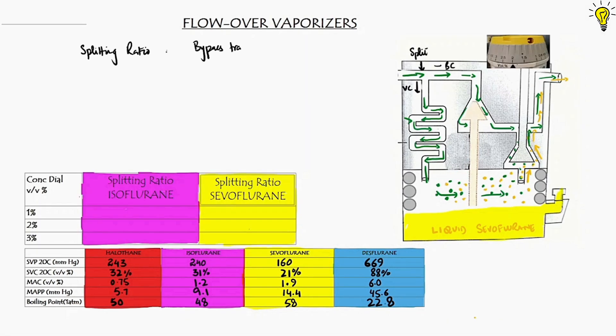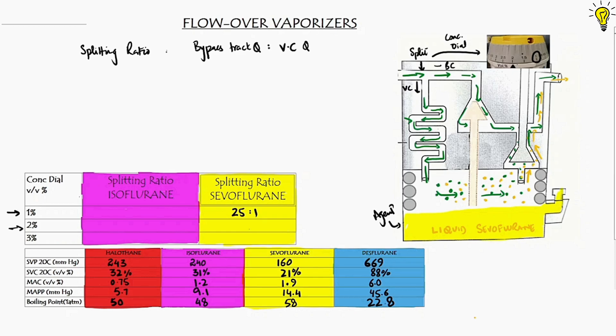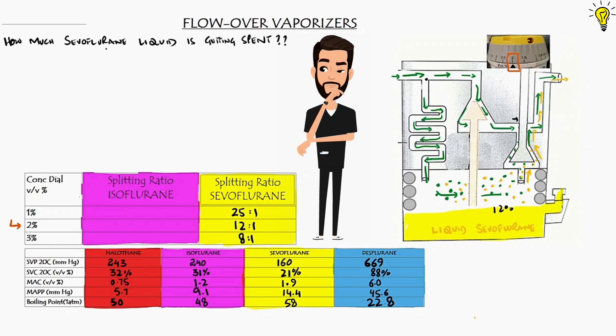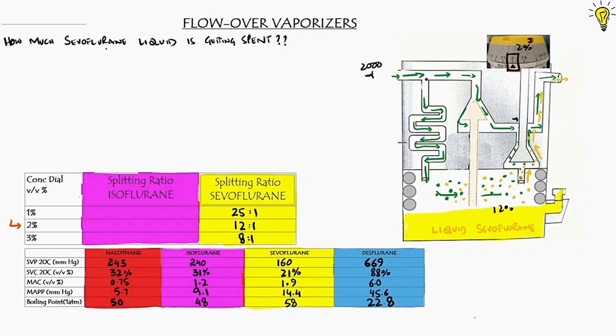The splitting ratio is the ratio of bypass flow to vaporizer chamber flow, directed by the concentration dial settings. Since it is agent-specific, the diversion ratio differs for different gases. For sevoflurane specifically, at 1% setting, the main flow is split into 25 parts bypass track to 1 part vaporizing chamber. At 2%, more flow is directed to the vaporizer chamber — 12 parts to 1 part. At 3%, the splitting ratio becomes 8:1.